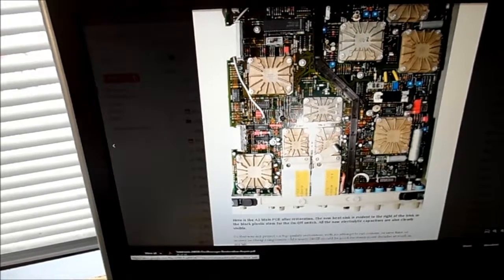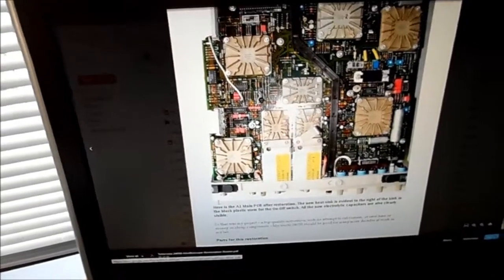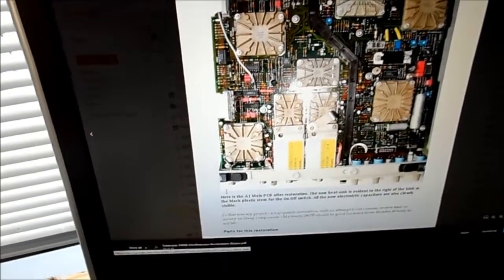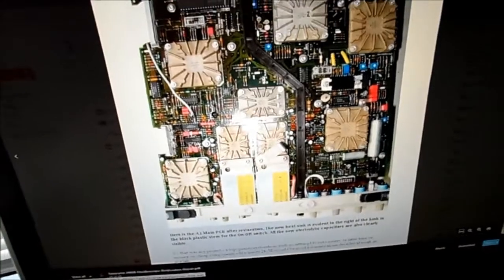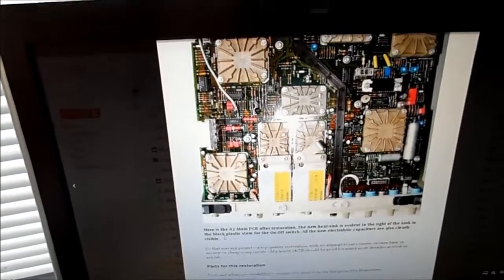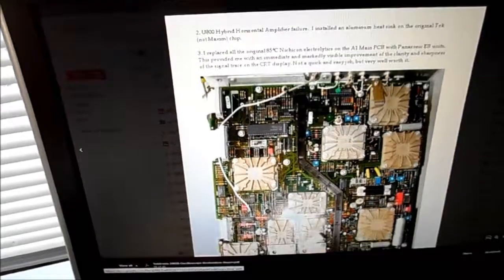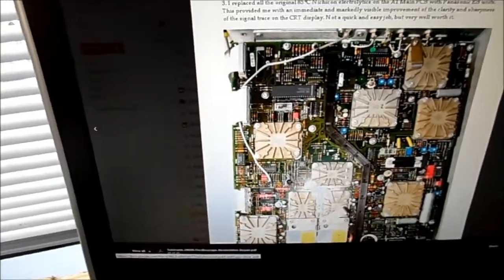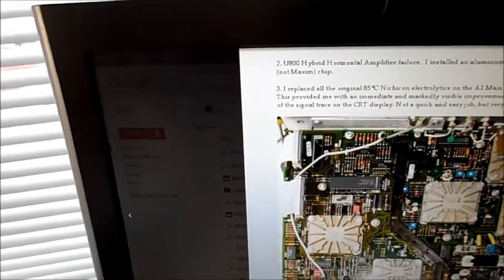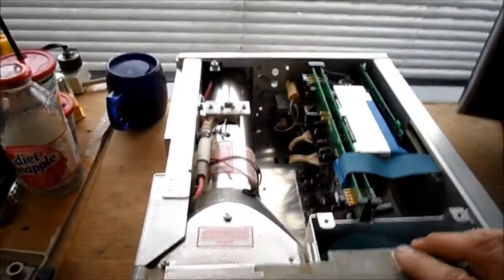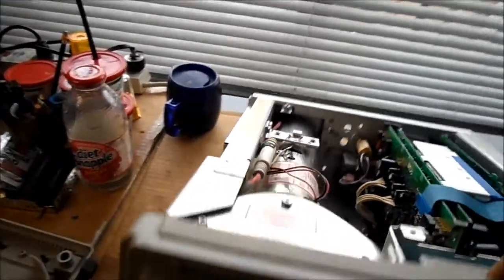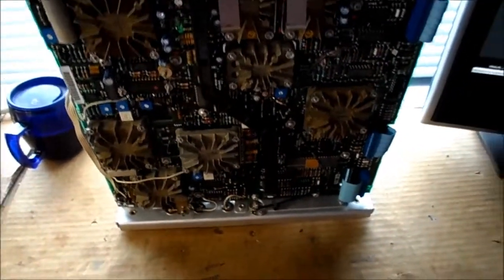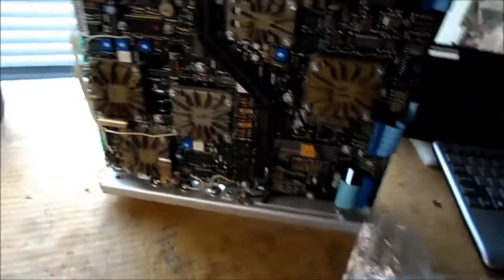I want to mention the other Achilles heel of the scope. This chip right here is the horizontal sweep chip. And he's gone ahead and put a heat sink on it because this used a lot of hybrid chips exclusively made from Tektronix that are no longer available. So he does say the U800 hybrid horizontal amplifier failure. These scopes are prone to that. This one does not have that problem, but I'm toying with the idea here of placing a heat sink on that horizontal deflection chip.